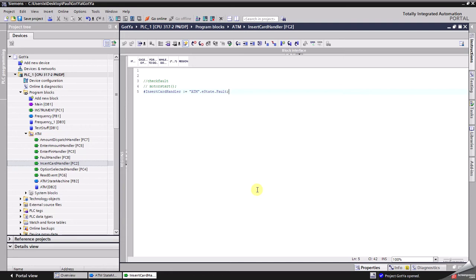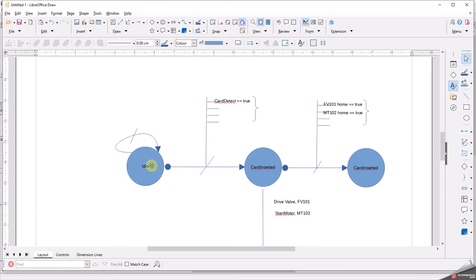The design pattern that sits at the top in the PLC world is called a state machine — something that moves from state to state to state. For example, you're making a cup of tea, that's one state; you walk to the front room, that's the next state. In machine terms, a valve in the home position is one state, valve in the out position is the next, and a part detected is another state.